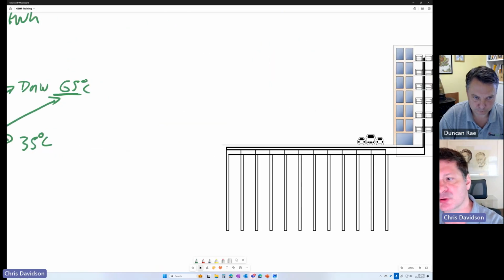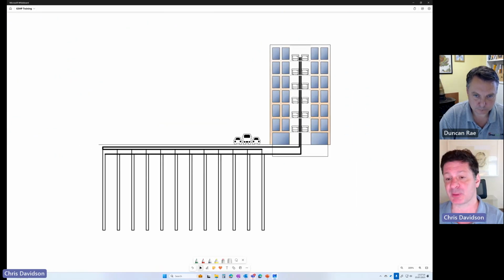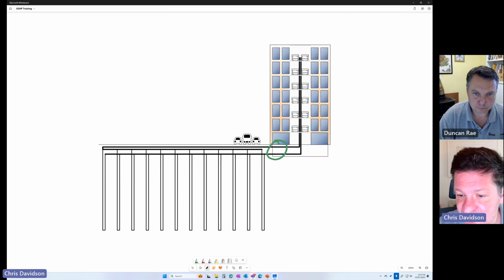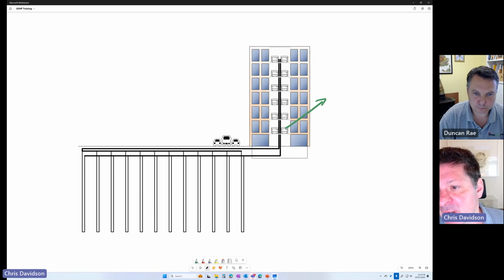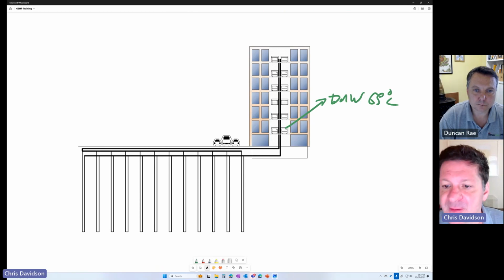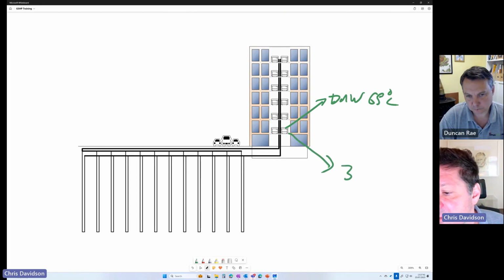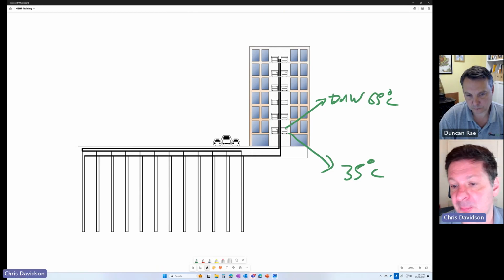Now we can contrast that with a distributed heat pump system. So right away you can see there's no central plant on this. There's not even any central pumping. The tiny little pump that's inside those little heat pumps is enough to drive enough fluid for that one heat pump around that loop on its own. And the benefit of this is we can now run at our domestic hot water temperatures at 65 degrees. We can then turn off that domestic hot water and run down at 35 degrees C for our space heating. We could also reverse that heat pump and provide cooling.